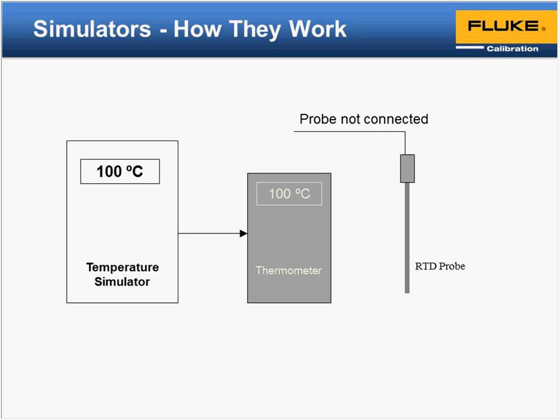So, the simulator, how does it work? Well, basically, in this case, you disconnect your probe and connect the temperature simulator to your thermometer. It goes back to that note a few back of a potential error not being considered by the probe. The simulator basically simulates the resistance of the probe. In our case, it's going to be ohms. And then the electronics piece of our thermometer is going to think it's seeing a probe.